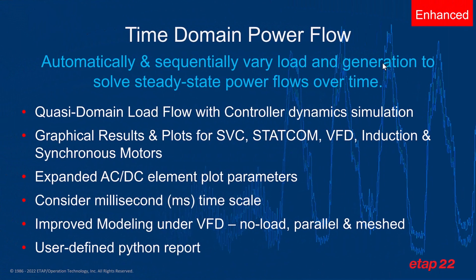Time domain load flow has also been improved significantly in ETAP 22. Time domain load flow itself allows you to automatically and sequentially vary the load and generation and solve the steady state power flows as a function of time. And the time can be a matter of minutes, hours, days, weeks, months, years, or multiple years. Time domain load flow essentially includes the ability to perform a quasi-dynamic load flow as well. This quasi-dynamic load flow can include the controller dynamics within the simulation, allowing you to essentially control or understand the time domain simulation from one step to another.